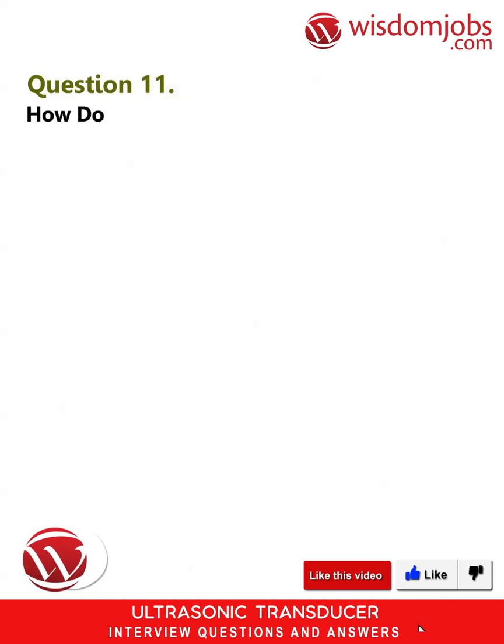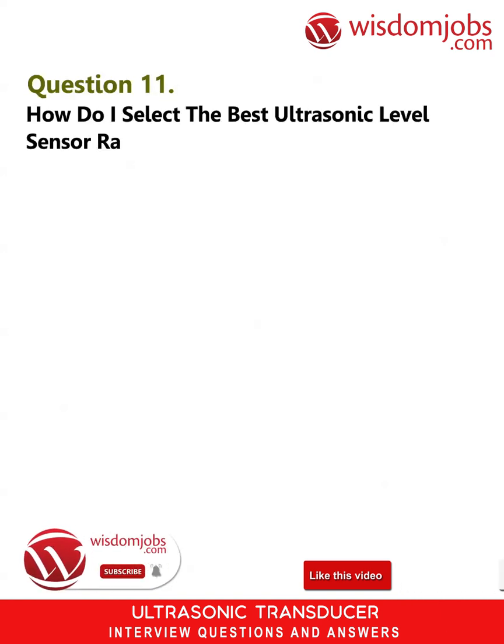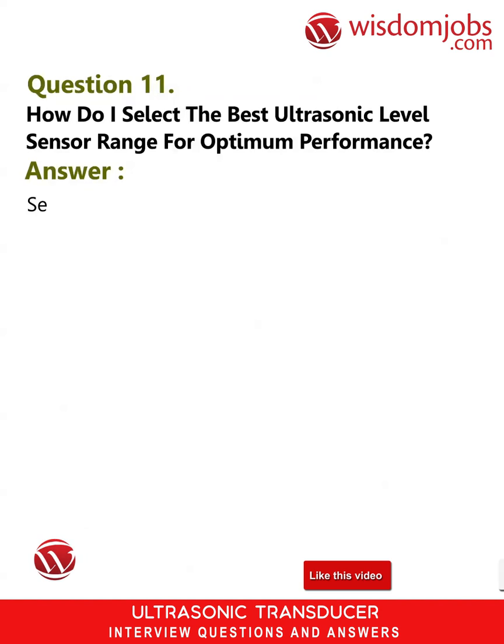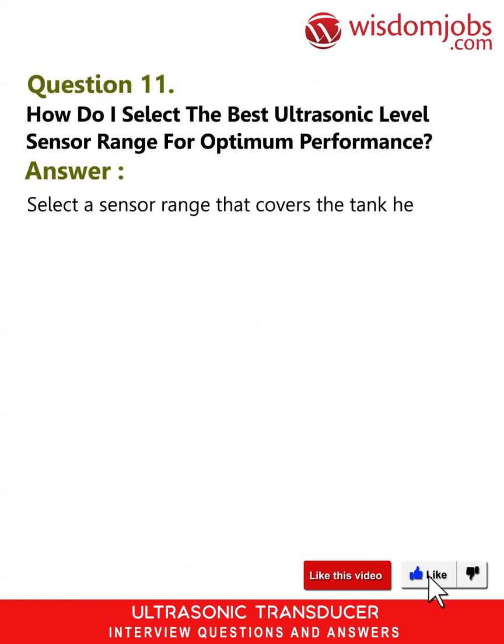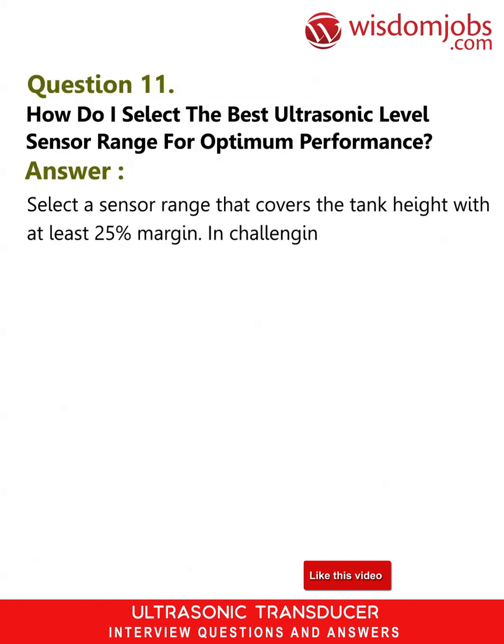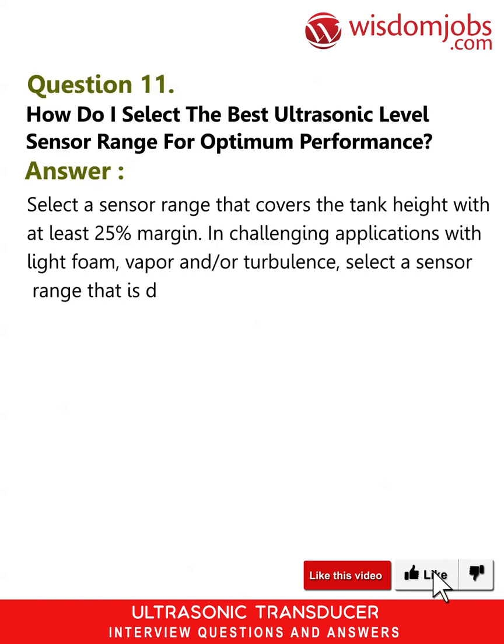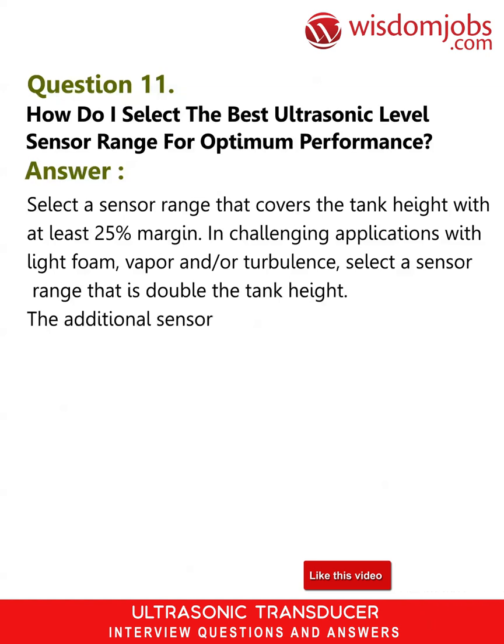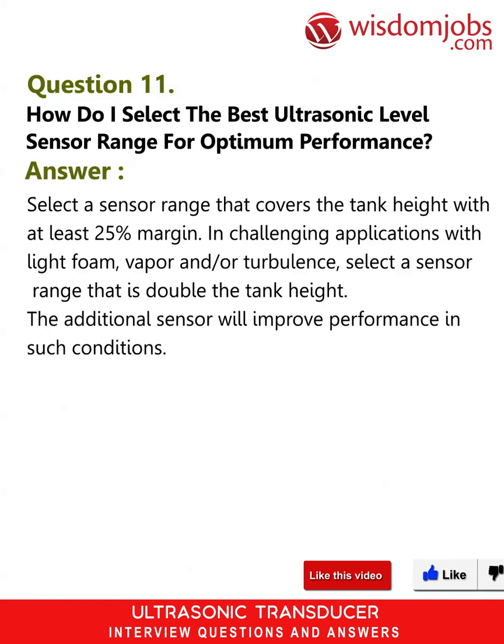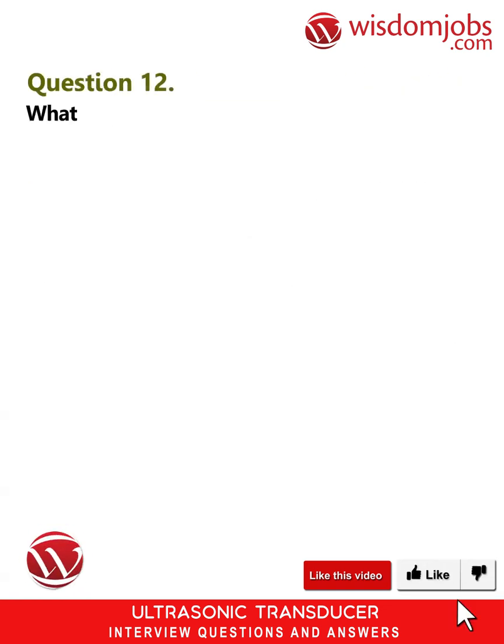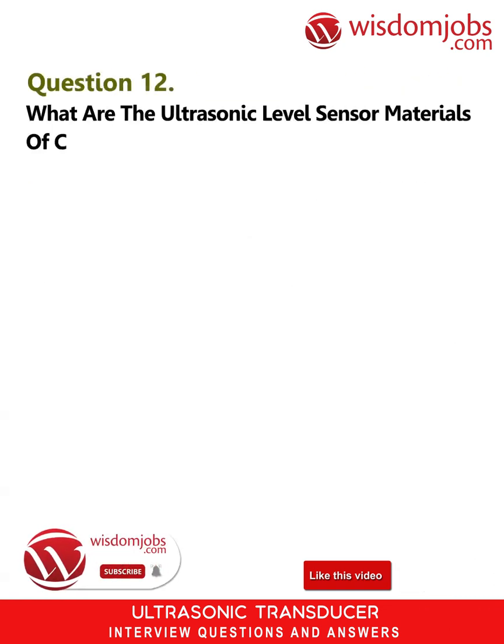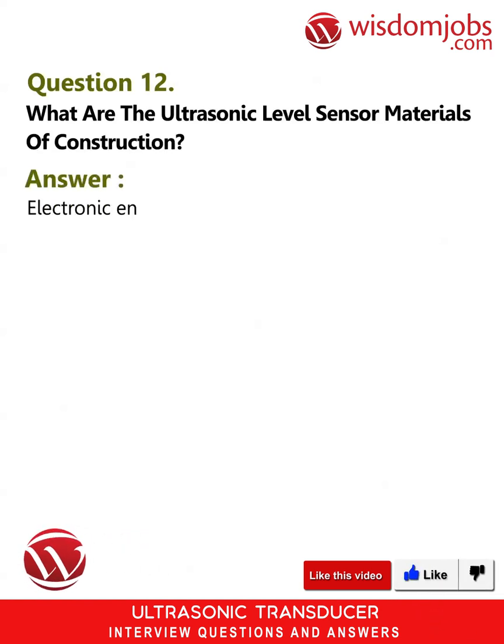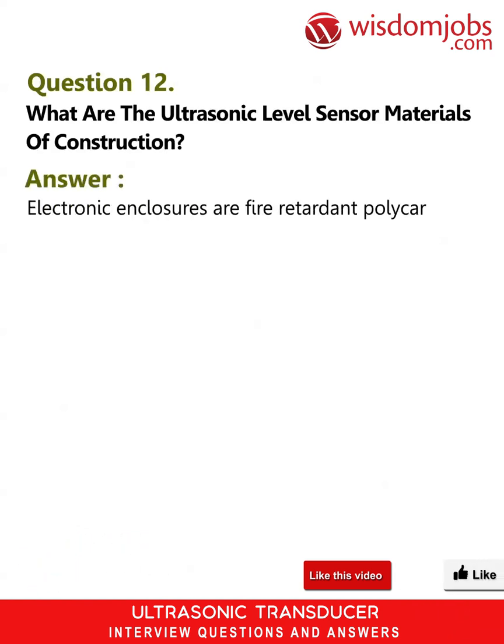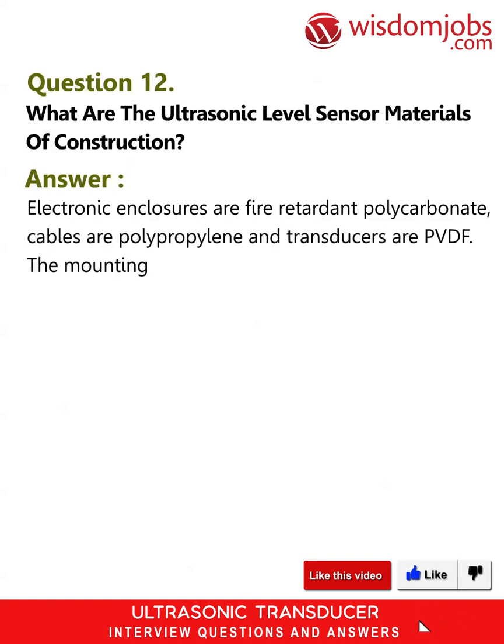Question 11. How do I select the best ultrasonic level sensor range for optimum performance? Answer. Select a sensor range that covers the tank height with at least 25% margin. In challenging applications with light foam, vapor and/or turbulence, select a sensor range that is double the tank height. The additional range will improve performance in such conditions. Question 12. What are the ultrasonic level sensor materials of construction? Answer. Electronic enclosures are fire-retardant polycarbonate, cables are polypropylene and transducers are PVDF. The mounting gasket is Viton.